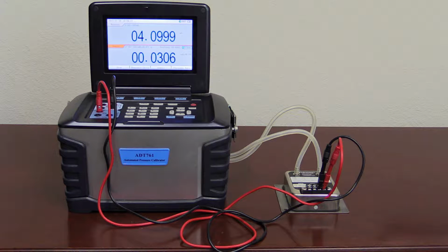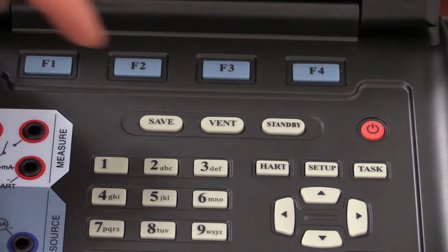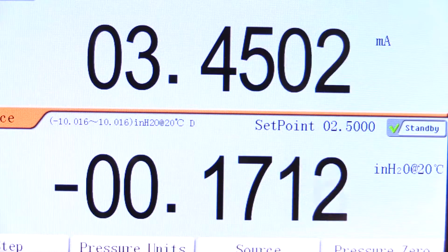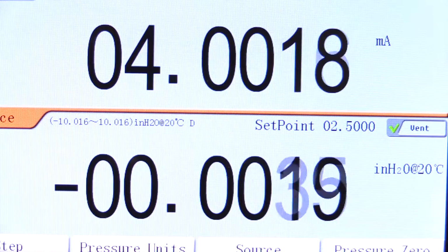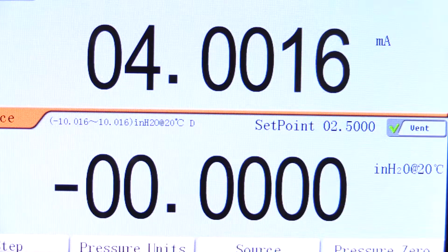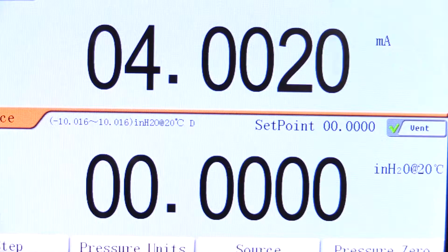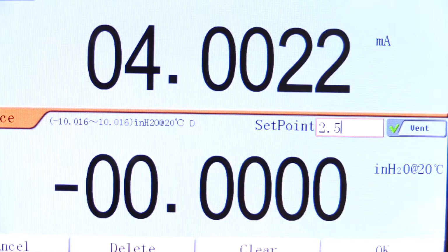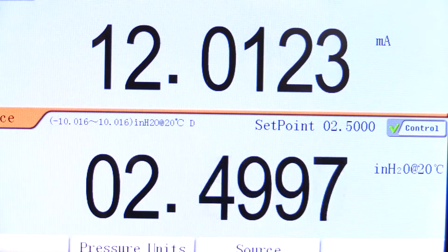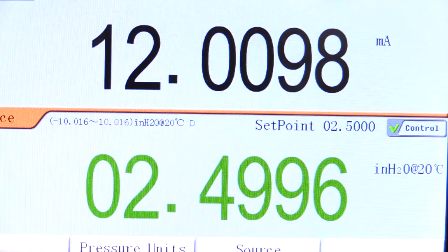For this calibration, we'll perform a 3-point test at 0, 2.5, and 5 inches of water. The first step is to vent to atmosphere and record the 0 point. To generate a pressure point, simply enter in the desired pressure into the calibrator, and it will automatically generate the pressure, and the reading will turn green when the pressure point is achieved and stable.